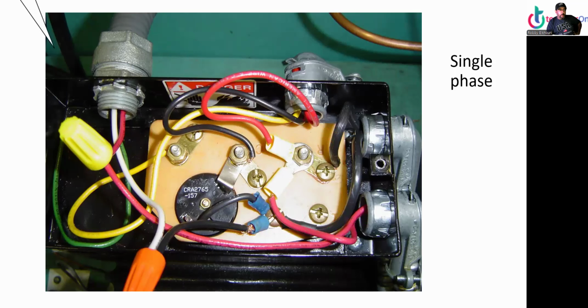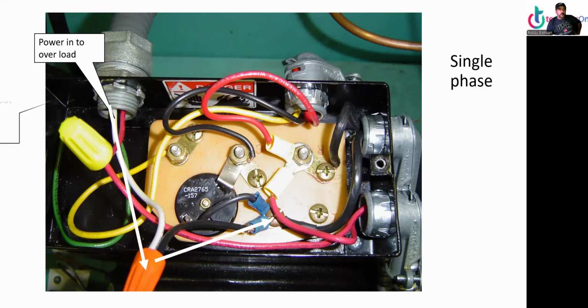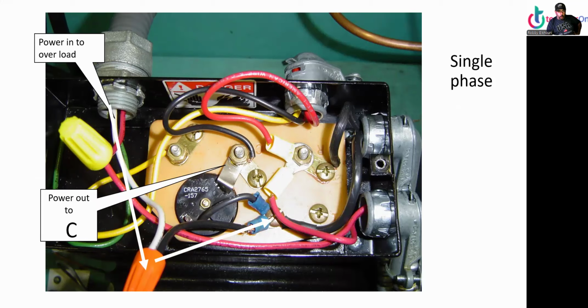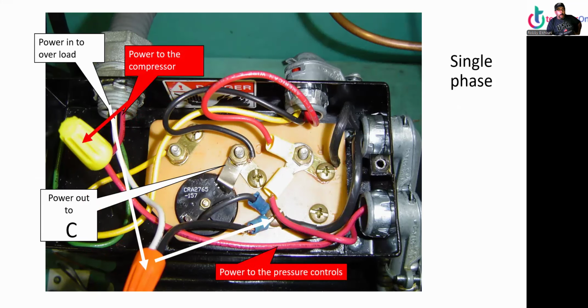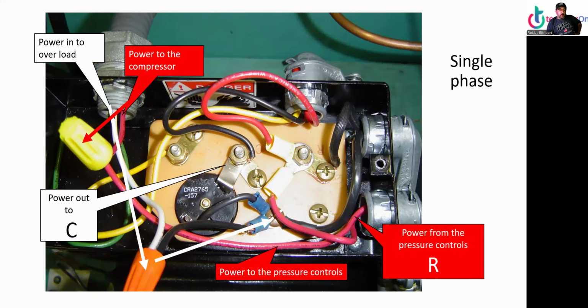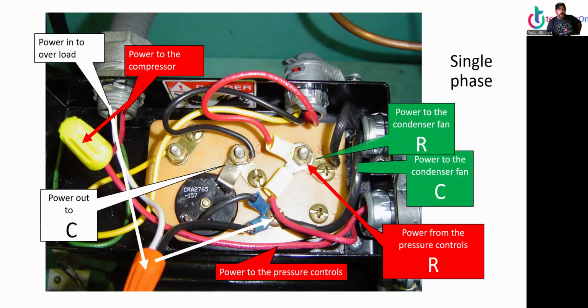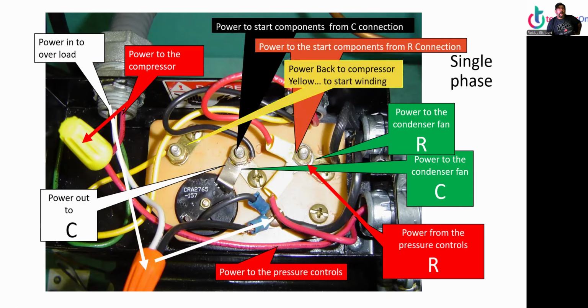Single phase compressors. So we have power in, and power in continues to the wire nut. Power goes to the screw, the overload screw, and power from the overload out to the common terminal. Power to the compressor in the red, and power goes to the pressure control, and power from the pressure control, red wire, goes to the run terminal. Okay, now in the run terminal, it goes to the fan, and the common goes to the fan. That's 220 to the fan. And power to the common run, and yellow, black, red, and yellow goes to the electrical starters. Okay, and the only thing yellow is back from the start winding, power from the yellow to the start winding from the start relay, from the current potential relay. All right, now let's move on.